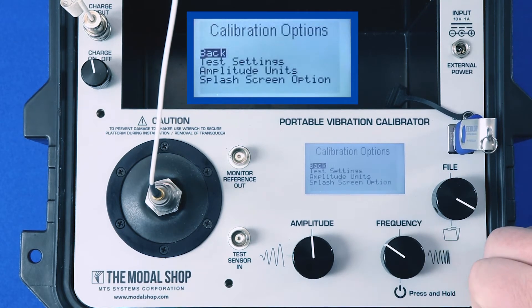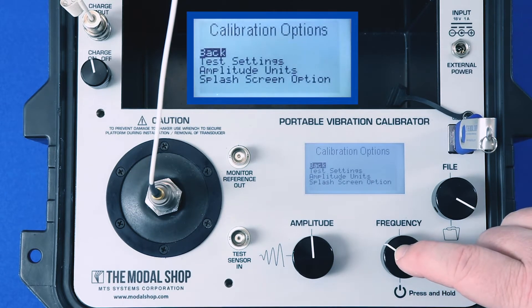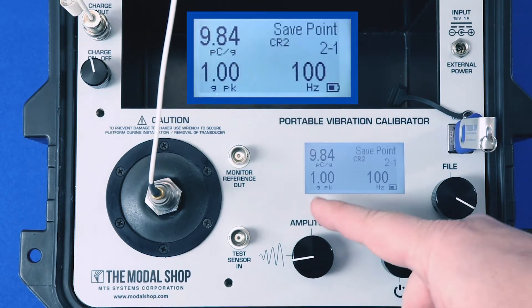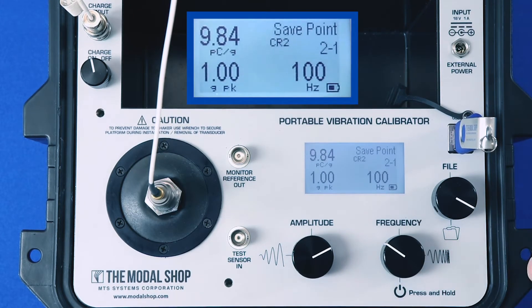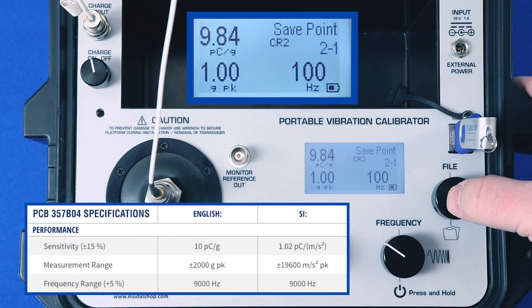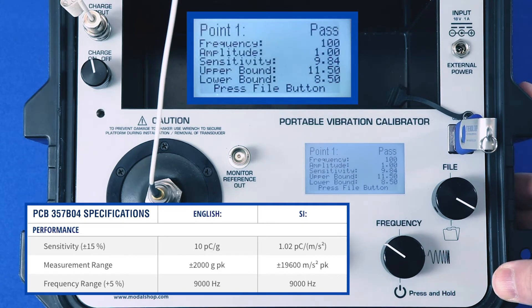Now I need to activate that test, which adds it to the list of tests stored in the calibrator's memory. I click activate and choose the appropriate test. Now I'm locked into that stepped sine test — I can't use the shaker in manual mode anymore. If I turn the amplitude dial, nothing happens. I'm locked into my pre-programmed test, which is going to start at 100 hertz.